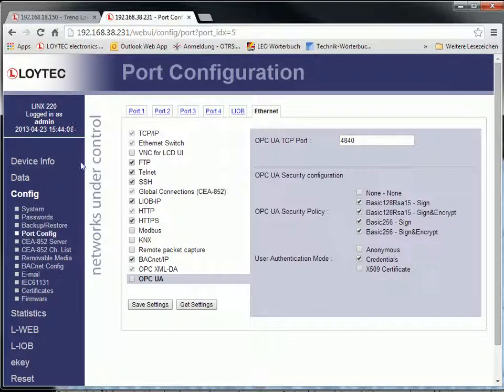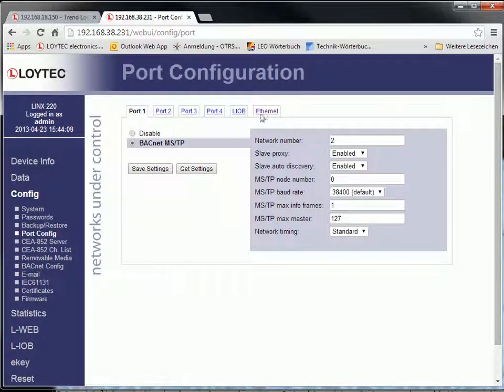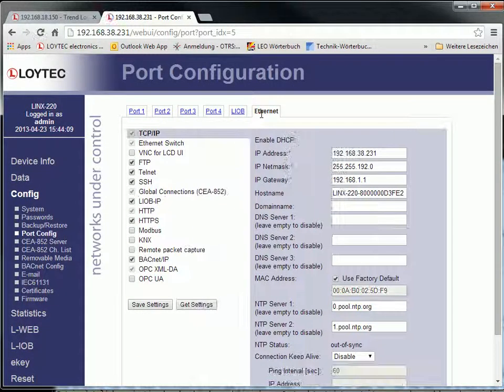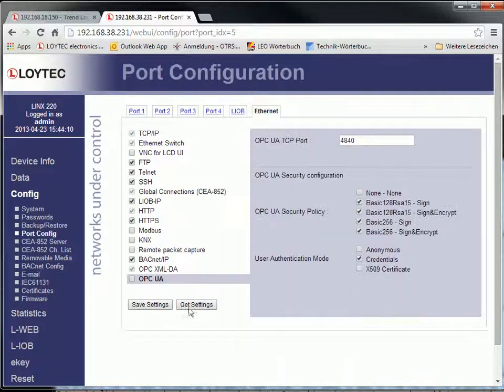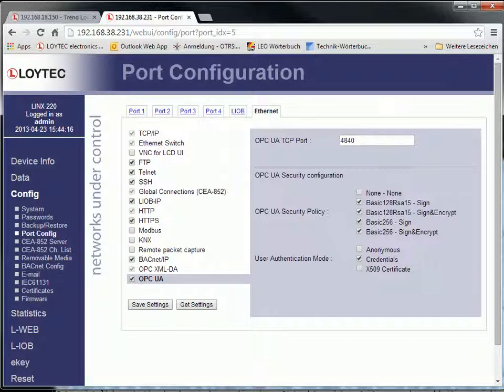The OPC server on the devices, which supports security, has been extended by an OPC UA server. This supports the OPC UA binary protocol and exposes the same OPC tags as the well-known OPC XML DA server. In addition, OPC UA offers superior security features as well as slimmer data transfers.